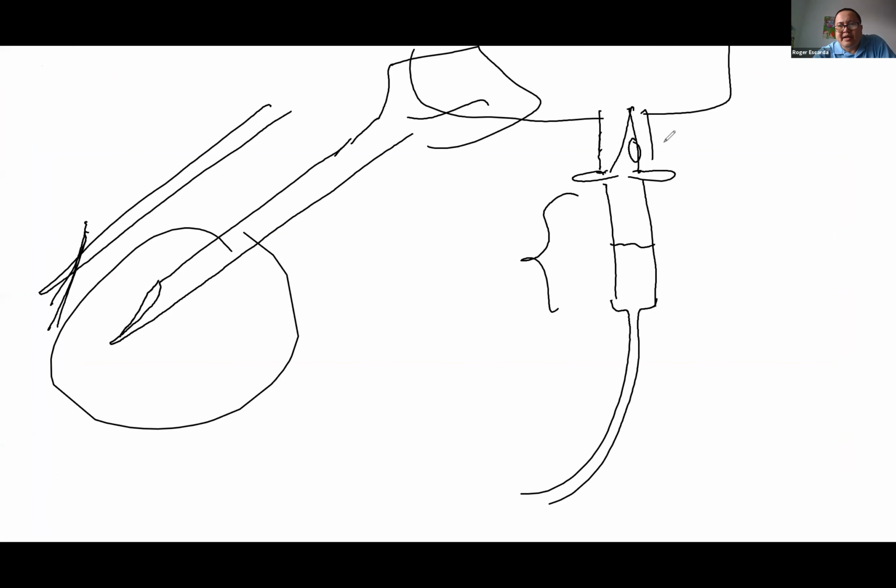If this is a blood bag, you don't want the blood dropping onto hard plastic, because the whole tubing is made of plastic. You want the blood to drop on liquid so that it doesn't get damaged. If it drops on a solid plastic surface, of course you're hemolyzing the blood. Red blood cells are very fragile. They easily break.